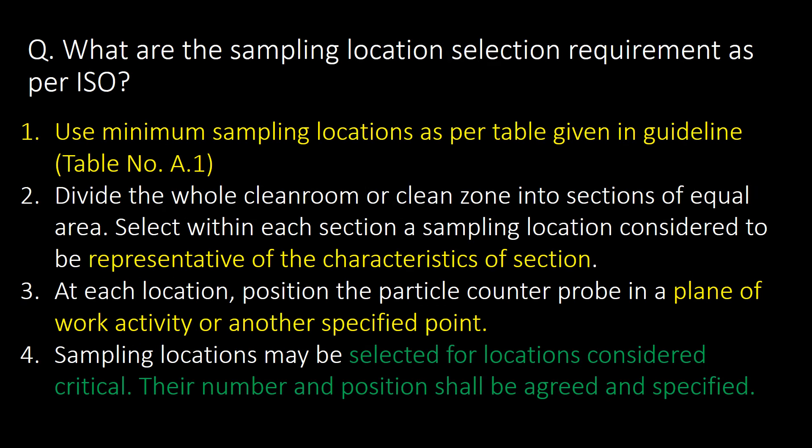What are the sampling location selection requirements as per ISO? Requirement one: use the minimum number of sampling locations as per the table given in the guideline — Table A.1 — which we saw in the last question's answer. Requirement two: divide the whole cleanroom or clean zone into sections of equal area, and select within each section a sampling location considered to be representative of the characteristics of that section.